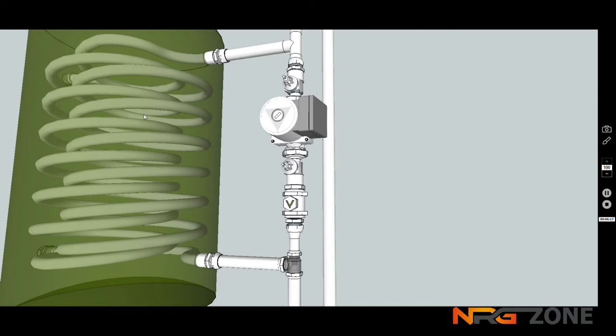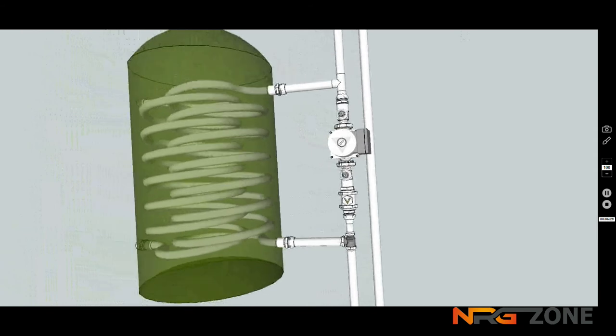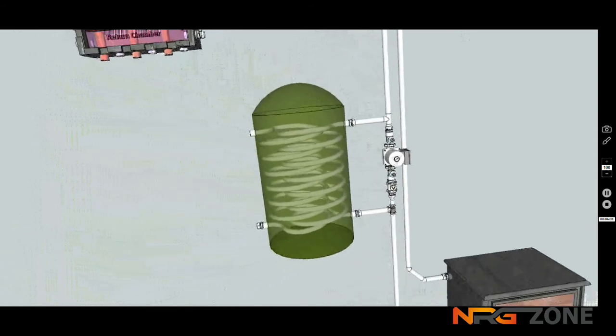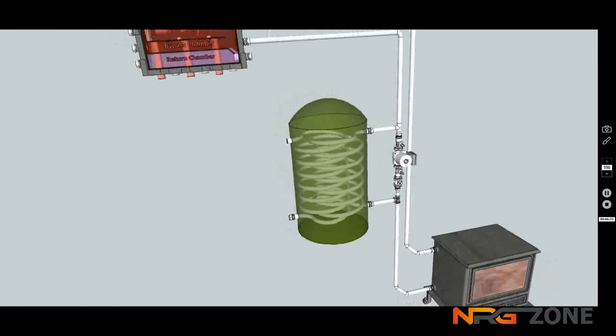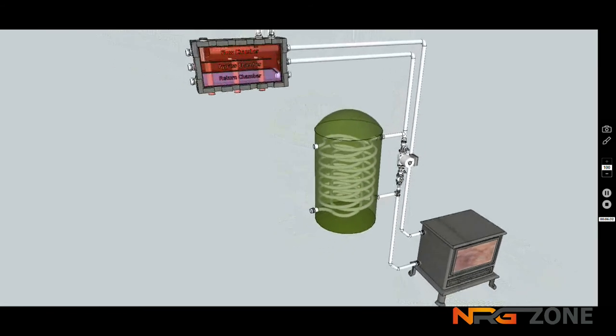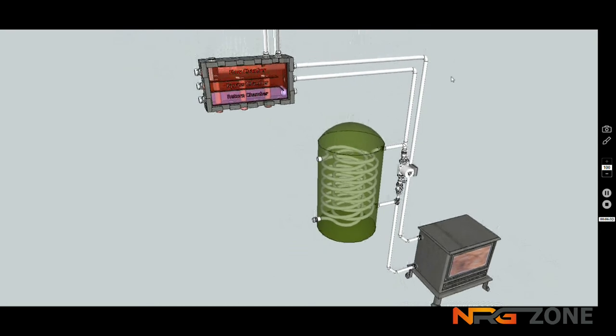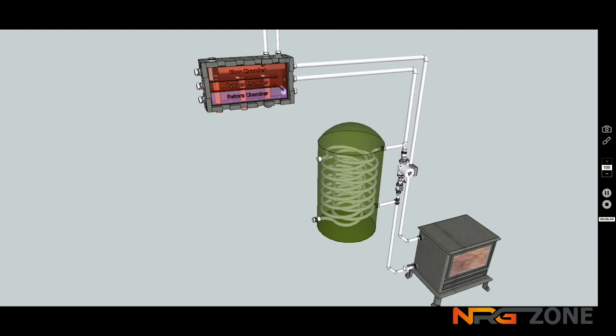That vacuum will suck the water through the coil and down, and suck this water in front of the injector, and the injector then fires it down through and through the stove. So, in other words, we've increased the velocity of the system substantially. We're heating the water much, much faster, and we're delivering much more water through the stove, which will take away the full heat capacity of the stove.